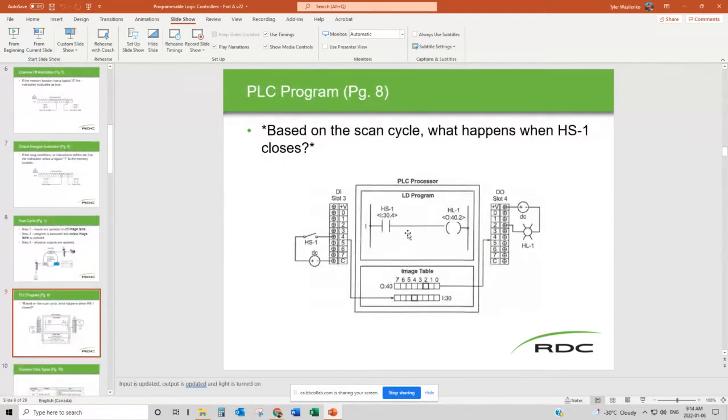So this leads us to our basic first little ladder diagram. Looking at a scan cycle, or what we just talked about in a scan cycle here, I want you to think about what happens when the hand switch number one closes. So here you have hand switch number one connected to the digital input card, which is located in slot 3 of our rack. And the switch itself is connected to channel number 4. The switch is open right now. So if we're looking at an operating program, this would look just like it does right now, as with this. Neither one of them would be energized. We close the switch. The I/O table in the card changes from a 0 to a 1. Because this is an examine on and it's looking for that 1, it says, hey, there's a 1 here now. I'm going to turn green. This will update the output table saying that this rung is now green. That means that we can turn on this output. The output will turn on green and it will energize a light. So hopefully we have no questions there. Any questions at this point?